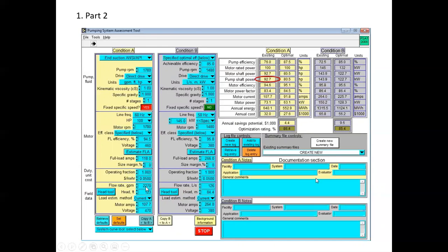Here's my flow rate now, 2270 from the pump curve, and it's 122.93, but PSAT rounds it, so it displays 123. My average motor amps and my average voltage here. And so this is my existing operation. I can see my pump's operating at 76% efficiency.